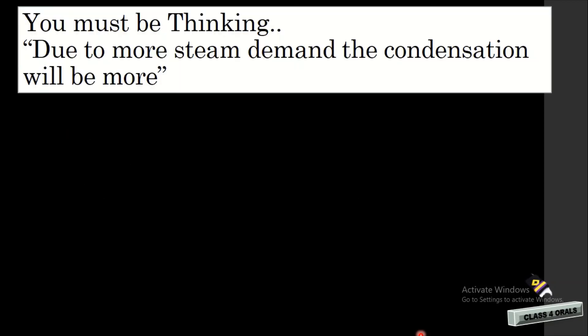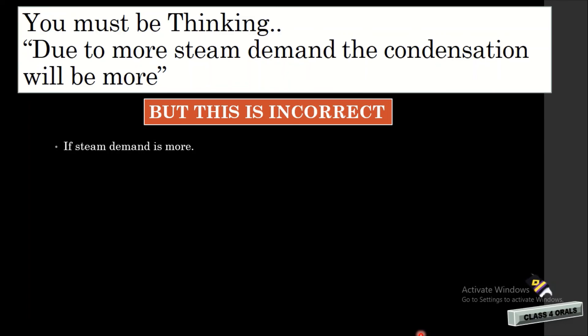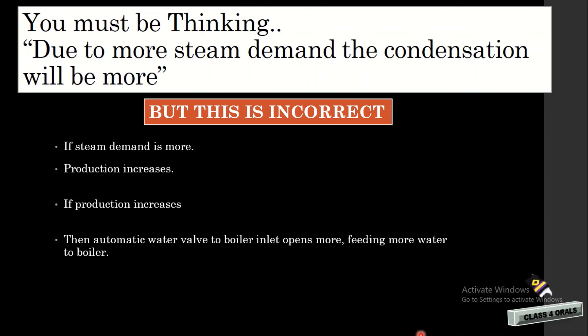One might think that the reason for cascade tank overflowing is more steam demand causing more condensation, resulting in overflow — but this is incorrect. If steam demand is more, that means production has increased. If production has increased, then the automatic water valve to the boiler inlet will open more and feed more water to the boiler, meaning the cascade tank will never overflow. So due to more steam demand, there will never be overflowing of the cascade tank.